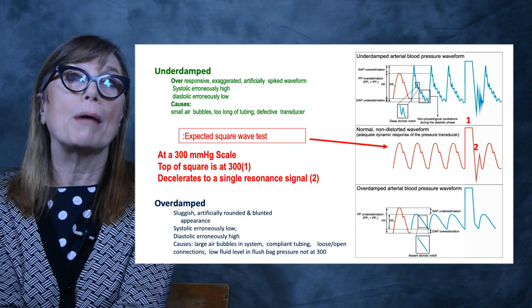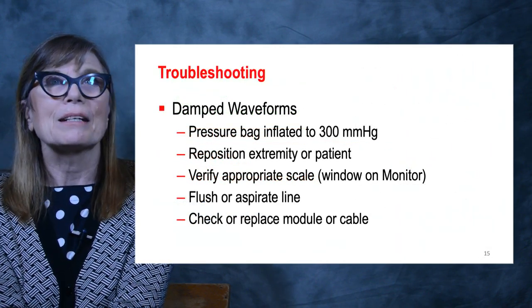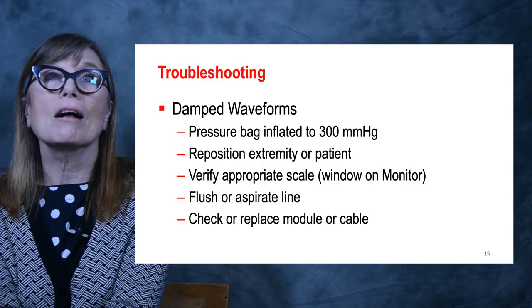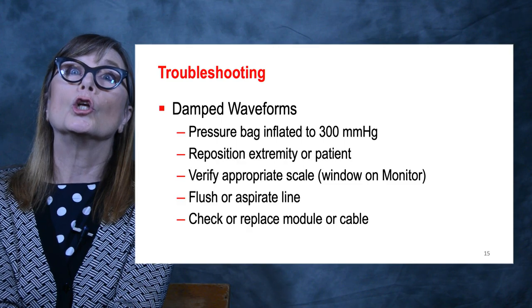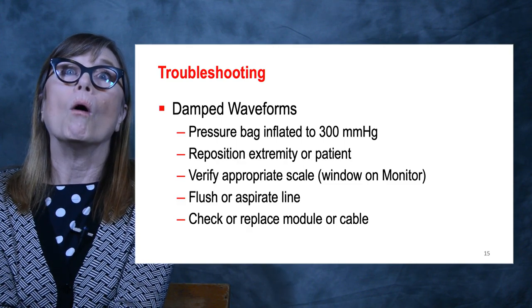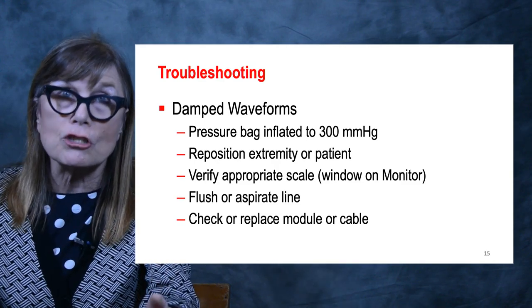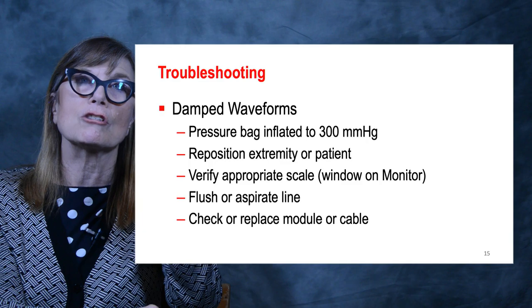That will help you have a better pressure waveform visualization. All right. So just remind yourself, troubleshooting, most important, a damped waveform looks like hypotension. So always make sure your patient is okay and then check your system, just as I've mentioned before.